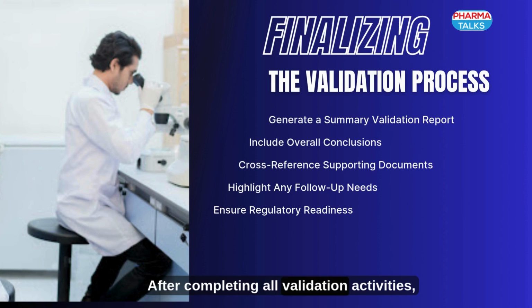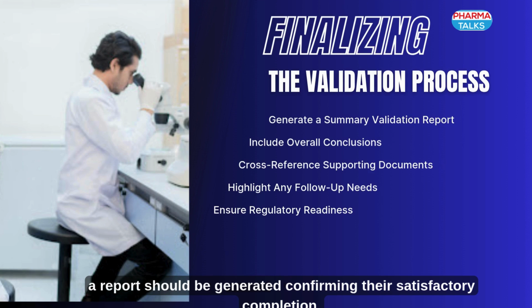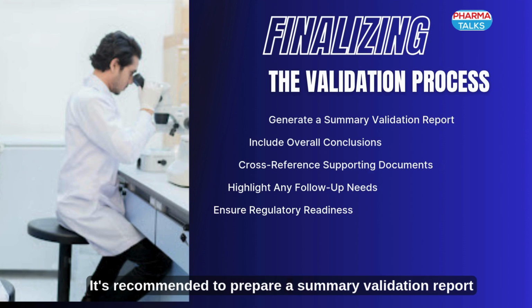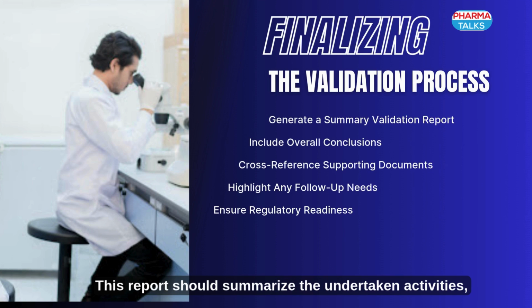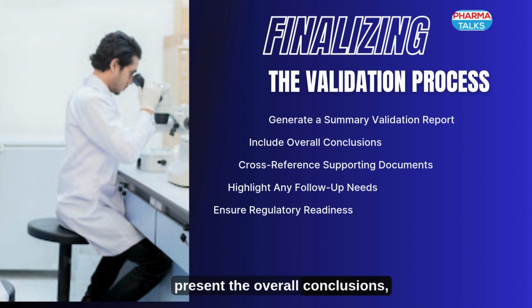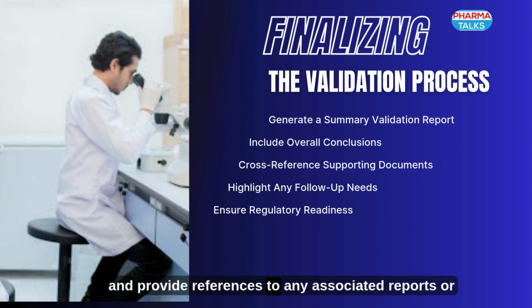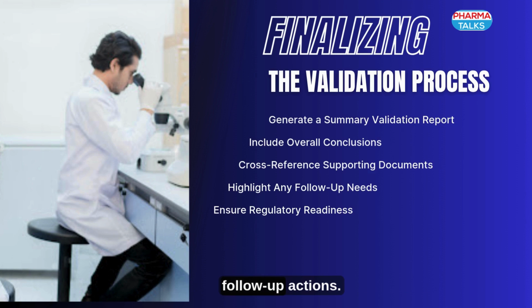After completing all validation activities, a report should be generated confirming their satisfactory completion. It's recommended to prepare a summary validation report or master validation report. This report should summarize the undertaken activities, present the overall conclusions, and provide references to any associated reports or follow-up actions.